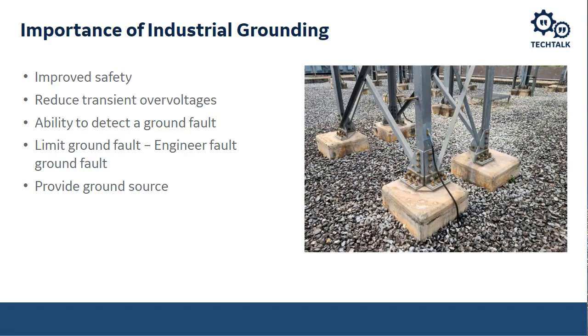You also want the ability to detect a ground fault before a multi-phase fault. So when a ground fault happens, you want to be able to detect that ground fault immediately and either cause an alarm or cause a trip, before it evolves into a multi-phase fault. Because once it evolves into a multi-phase fault, then we go into issues of damage to the equipment, permanent damage might happen to equipment, and safety issues. If impedance is introduced, we can limit ground fault current and the associated damage that these ground faults can cause.